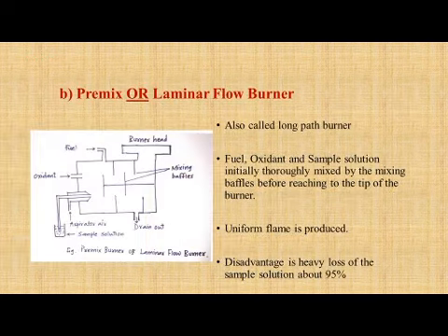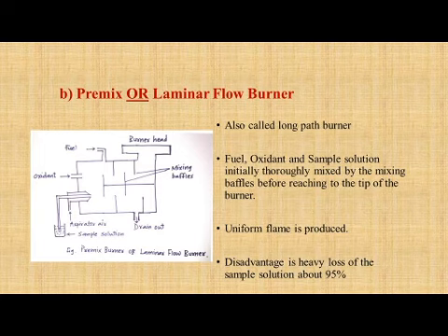The second important burner is the premix or laminar flow burner. In the picture of the premix or laminar flow burner, we observe all the components: fuel and oxidant entries, sample solution, mixing baffles, and the burner head, and at the right-hand side in the downward direction there is a drain.